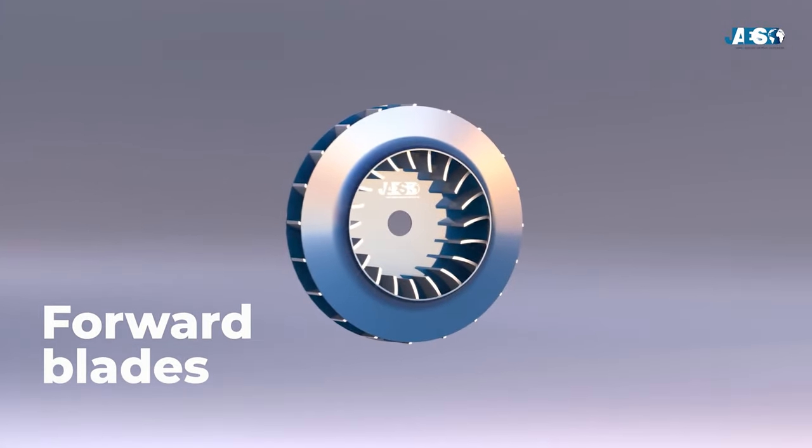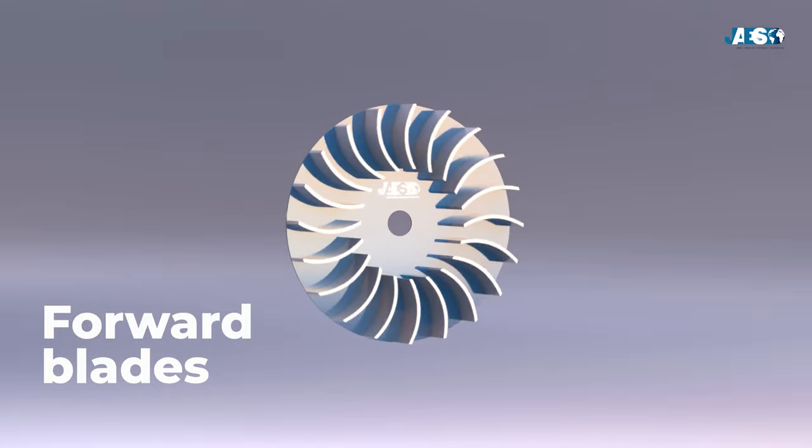Industrial fans with forward blades are characterized by a higher number of small blades close together, facing the direction of the rotation. They can move large volumes of air at a low speed, and they are recommended for applications where a constant air flow rate or an air delivery with constant pressure is necessary.